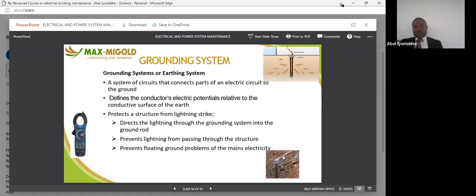An example is this one you can see very well, a bit burnt. What goes through the earth cable is nuisance current, unwanted or bad current, that leaves your installation. If you don't have a good earthing system, it will start damaging your equipment. So when there is a fault current within your installation, it passes through this place to the copper rod and goes to the ground, because the earth will receive it. Earth is taken to be 0 ohms.